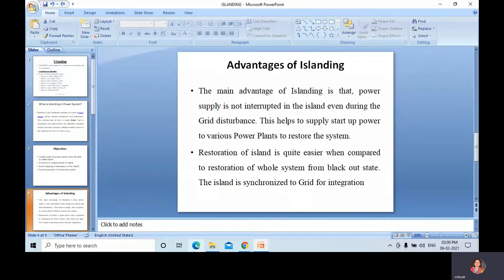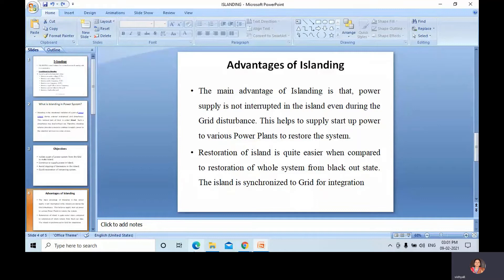An under-frequency relay is employed to sense major grid disturbances and initiate load shedding by opening designated feeders prior to islanding, to ensure a generation-rich island. Low grid frequency in combination with power flow towards the grid initiates islanding, and hence simultaneously trips all predefined lines to make the island.